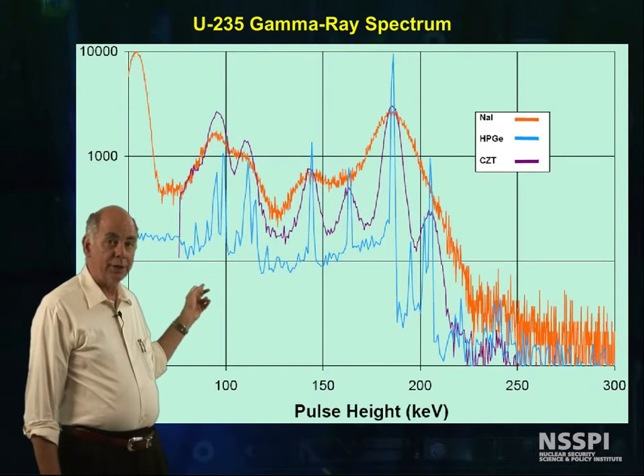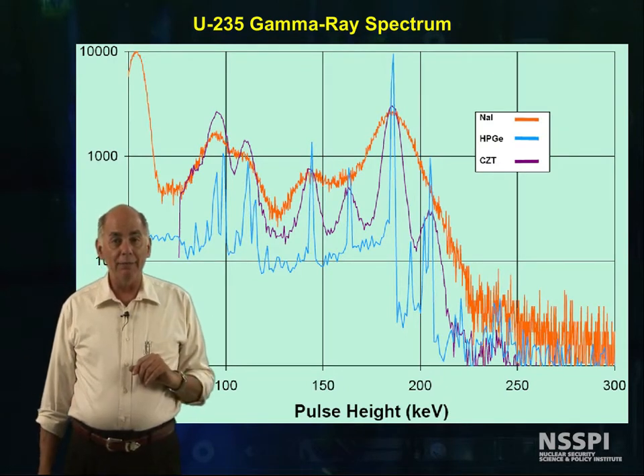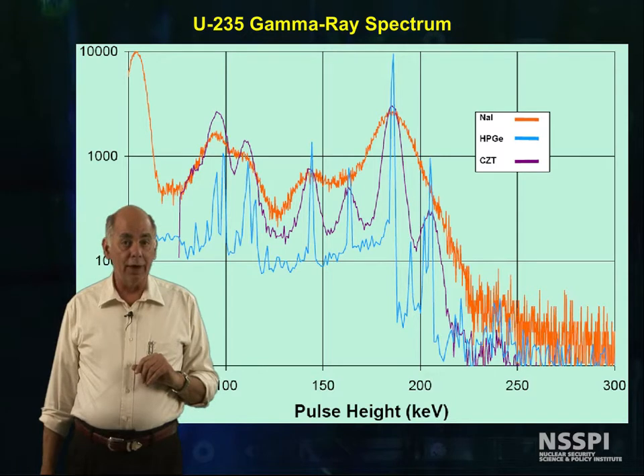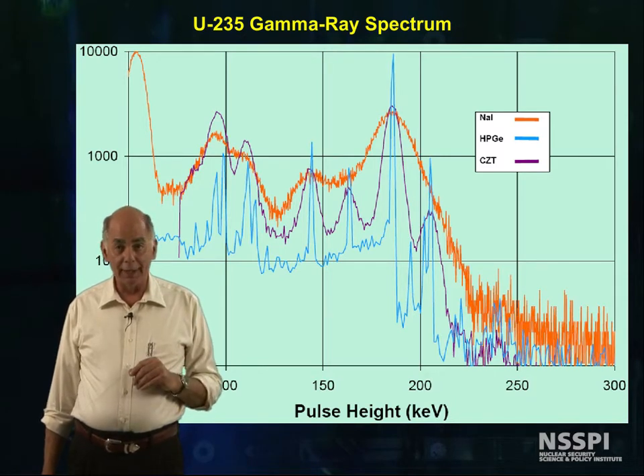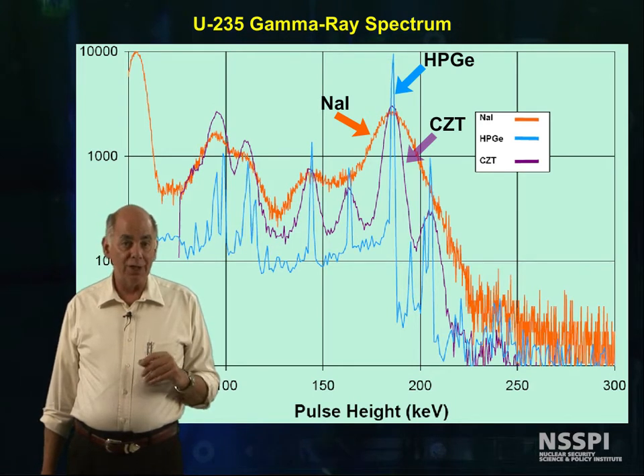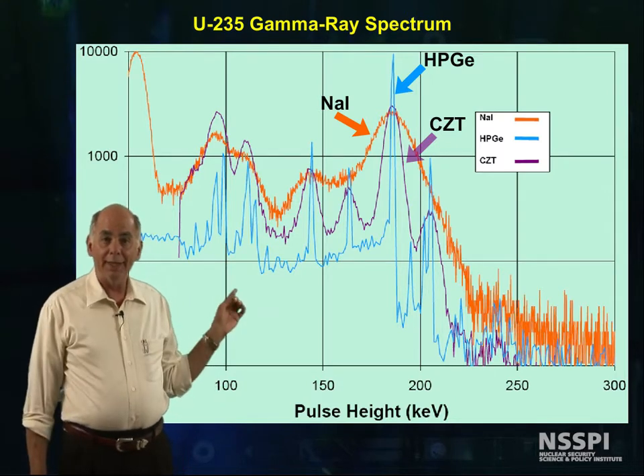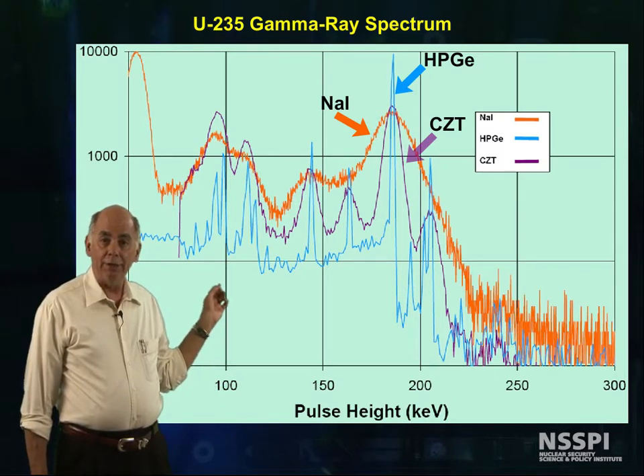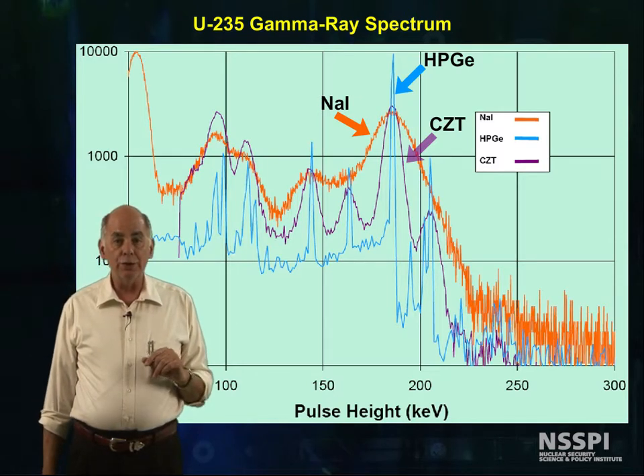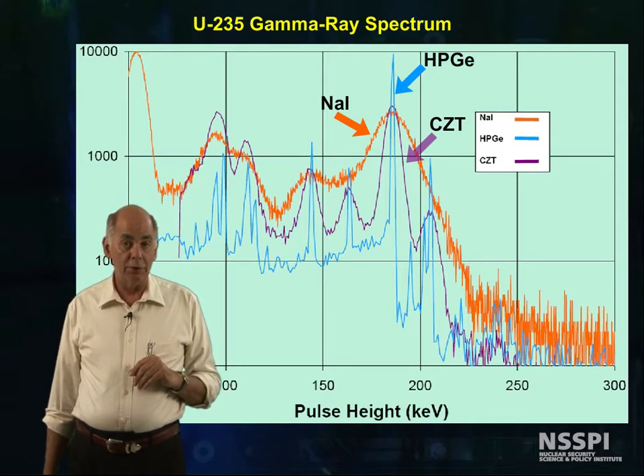Here's another example showing sodium iodide, high purity germanium, and cadmium zinc telluride, another type of semiconducting detector. The resolution of the cadmium zinc telluride is not as good as high purity germanium, but it's still far superior to sodium iodide. By looking at the three spectra, it's easy to understand that resolution is very useful in complex spectra like uranium and plutonium.